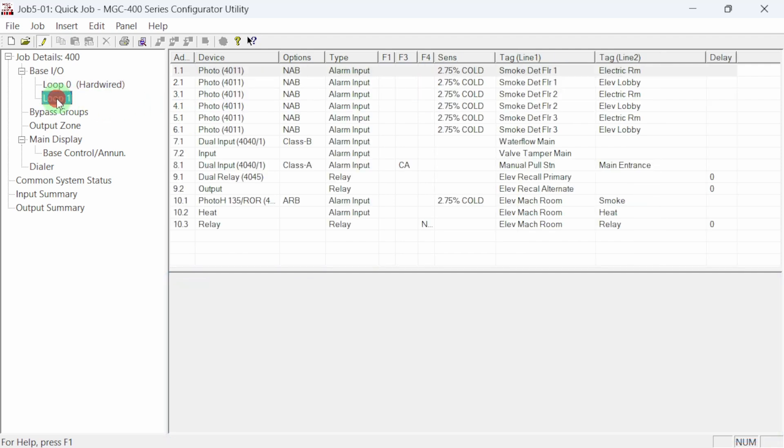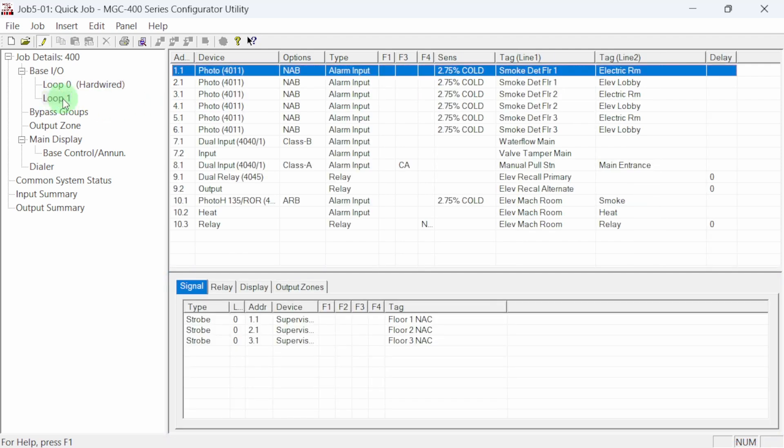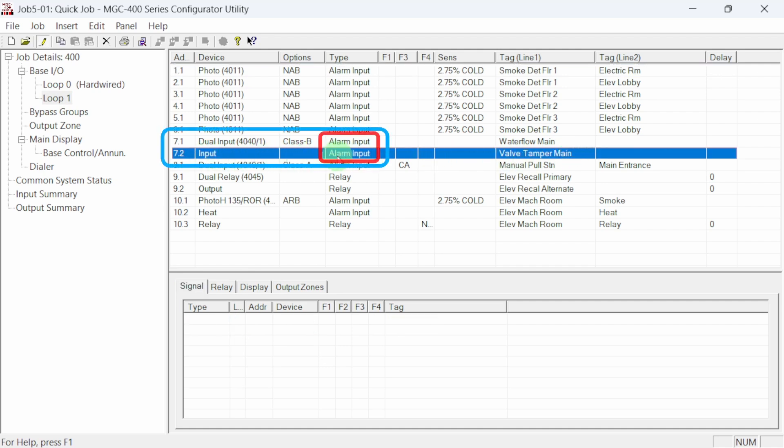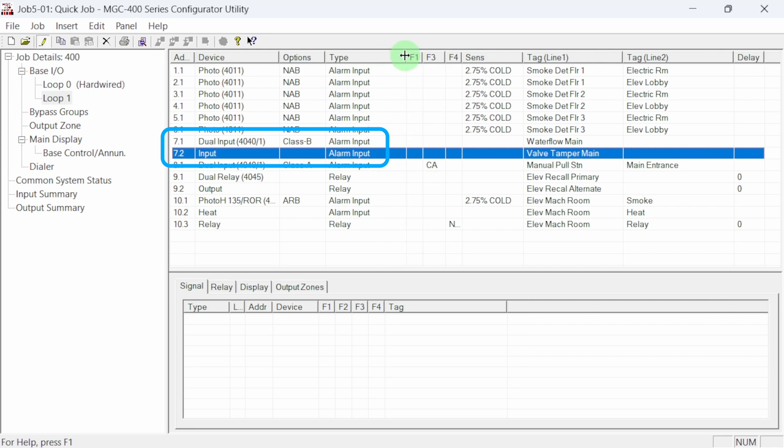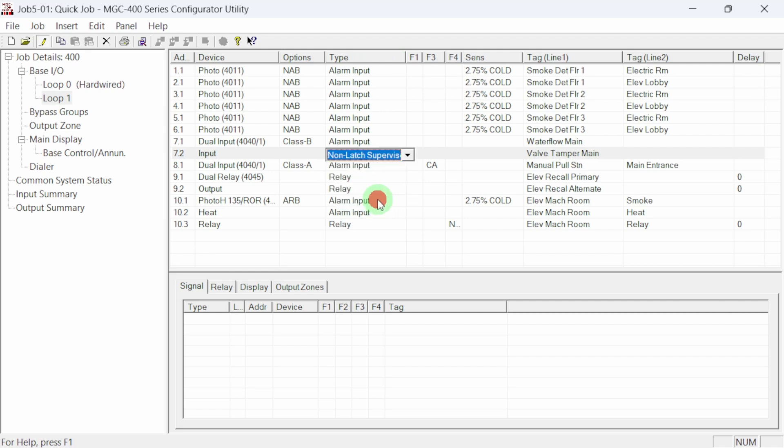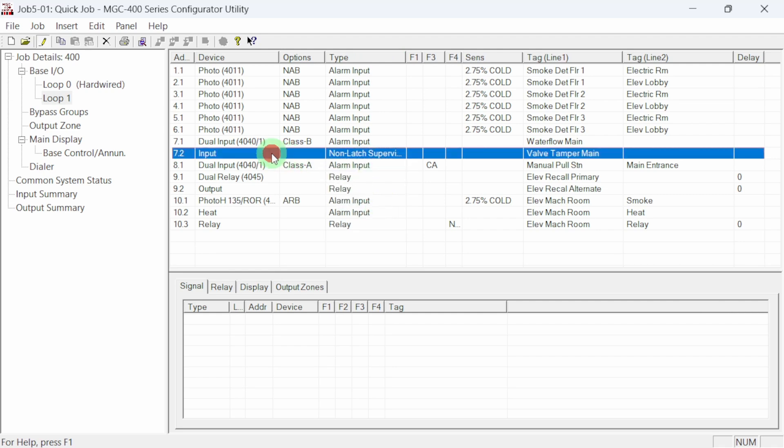Let's go back to the addressable loop one and make the correction to the valve tamper switch. When the dual input module was added, the default process was an alarm input. We want to change this input to be a supervisory type, not an alarm type. In the type column, clicking on the cell allows for the process to be modified. In this case, we'll choose non-latch supervisory as the process type.